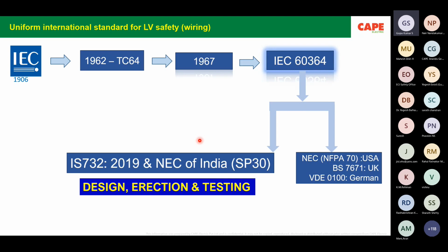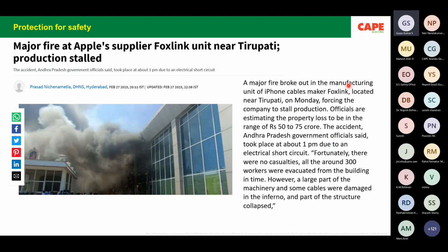The advantage of the NEC of India is that it is in line with the wiring regulations of any other country. For example, NFPA 70, the NEC of USA, BS 7671, VDE 100, and our IS 732 and NEC of India, all these are based on IEC 60364. IEC 60364 is the basic safety standard for design, erection, and testing of an electrical installation. Actually, I am in London today to attend a meeting of this IEC 60364 MT12, which is the maintenance group of experts responsible for maintaining the IEC 60364 Part 6 standard, which is on verification or safety audits.